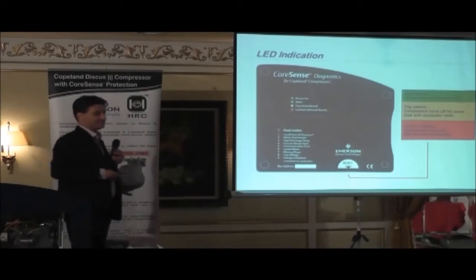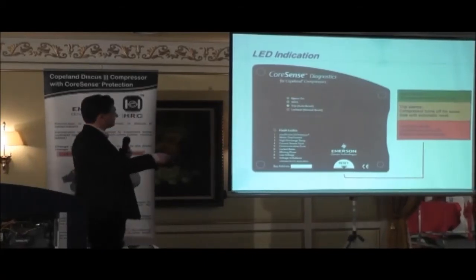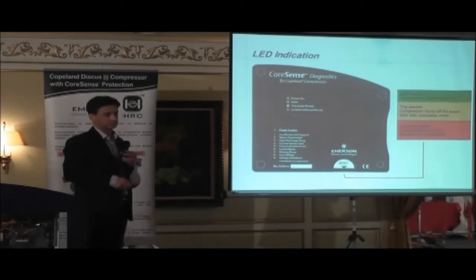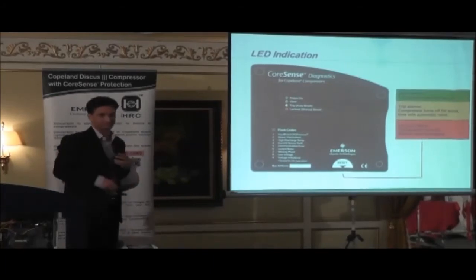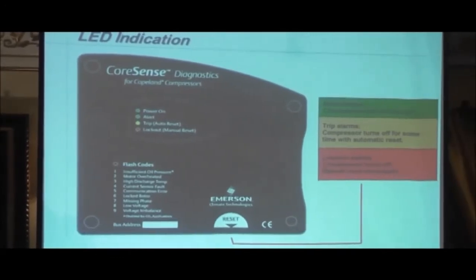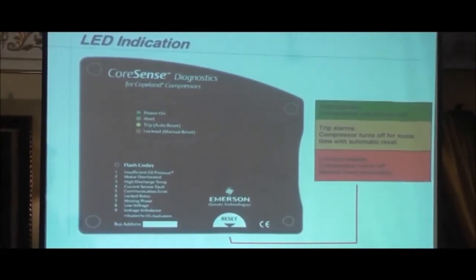We're now going to talk about the LEDs. Okay? When the diagnostic module is energized, this green LED is on, power on. We then have 3 alarm conditions. The green means I've got an alert. It's not bad enough to switch off the compressor, okay? But it will give an alert. Second is yellow. Compressor will switch off, but it will go through an auto delay and try and restart again. And then red means it's a lockout.